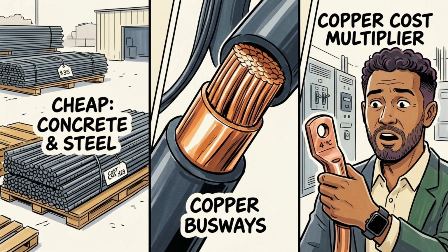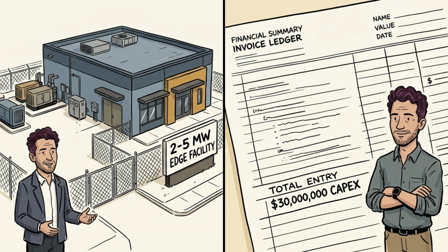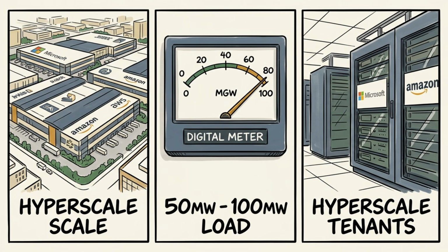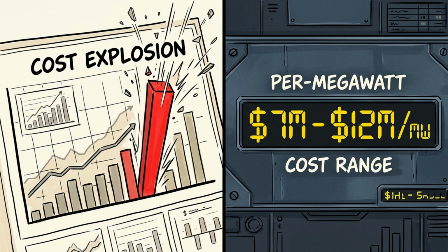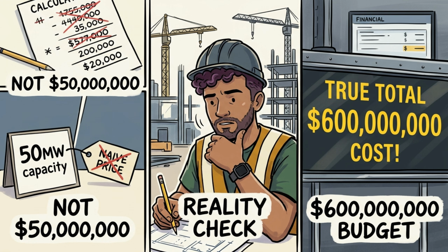You think concrete and steel are expensive? That's the cheap part. The real financial predator is hiding in the copper. A small regional edge facility with 2 to 5 megawatts of power might set you back $30 million. But if you want to compete for major cloud tenants with a 50 to 100 megawatt wholesale hyperscale facility, the kind built for Microsoft or Amazon, the cost explodes to somewhere between $7 and $12 million per megawatt. That means a standard 50 megawatt facility isn't a $50 million building, it's a $600 million mega project.